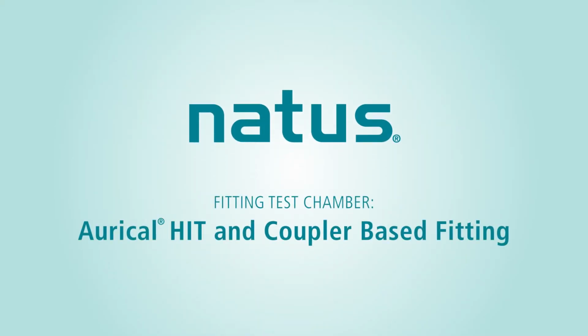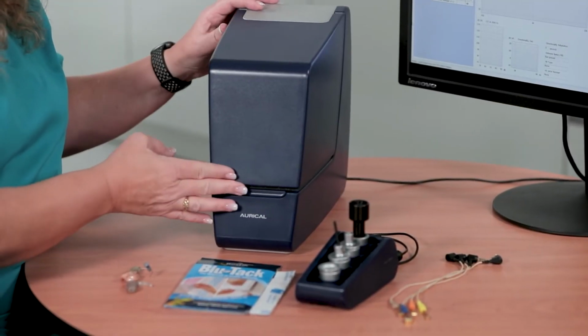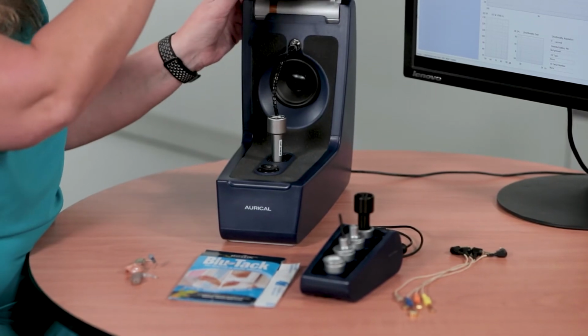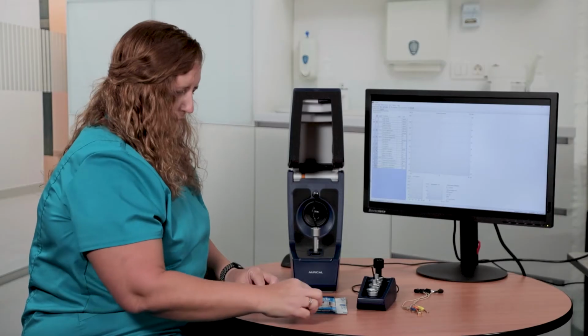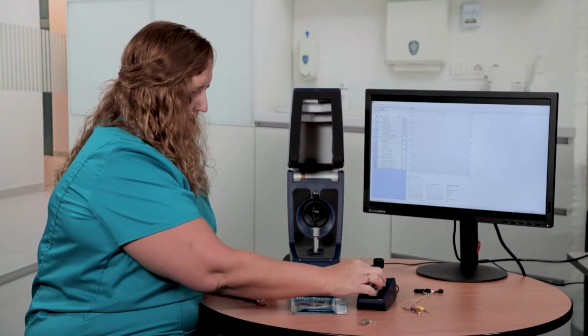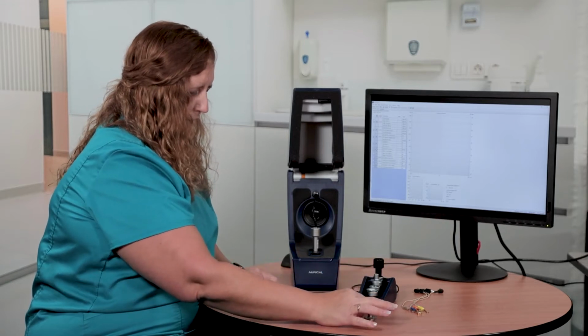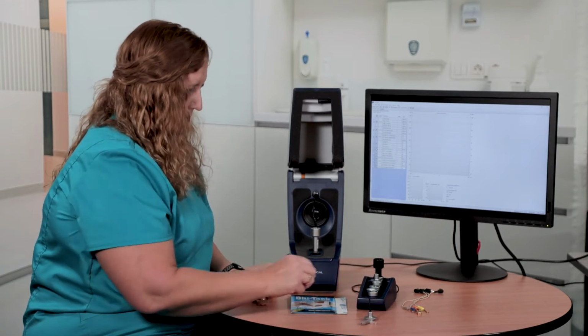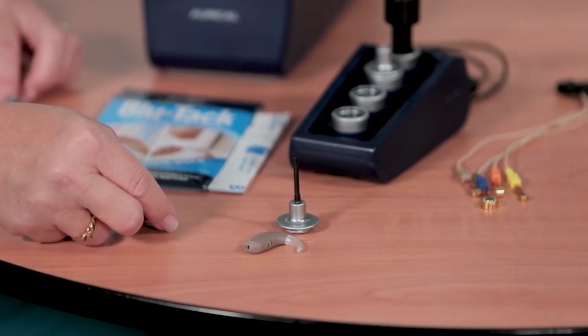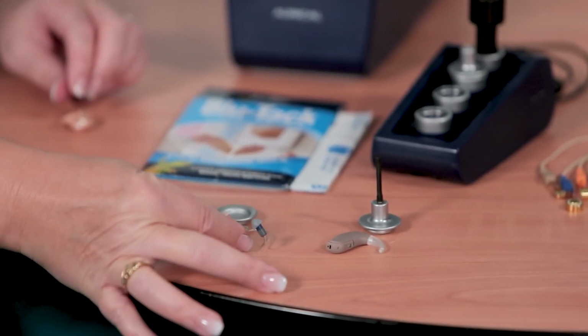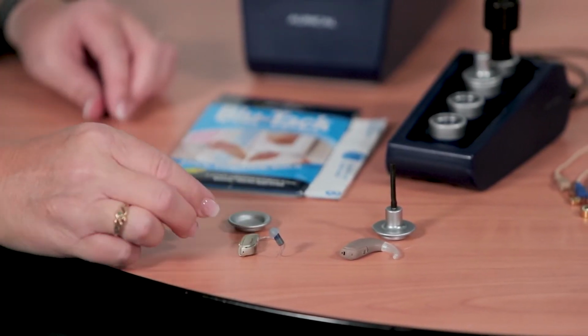Fitting test chamber, Aurical HIT, and coupler-based fitting. The Aurical HIT is designed to accommodate many different types of hearing aids. It can be used to conduct coupler-based fittings, run routine electroacoustic measurements, and verify advanced hearing aid features. It starts with coupling the hearing aid to the coupler assembly, using the correct adapter.